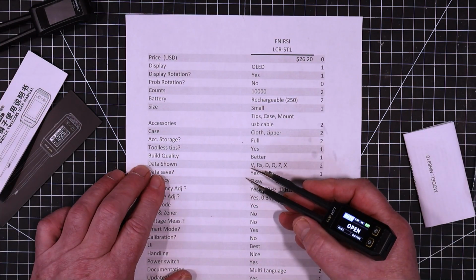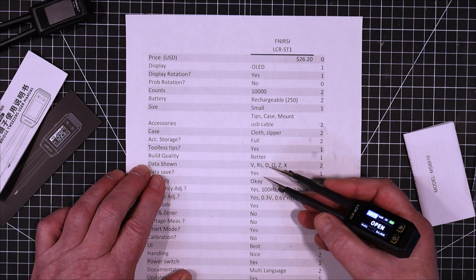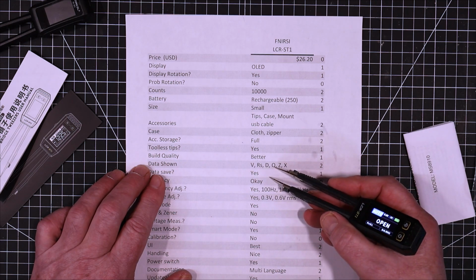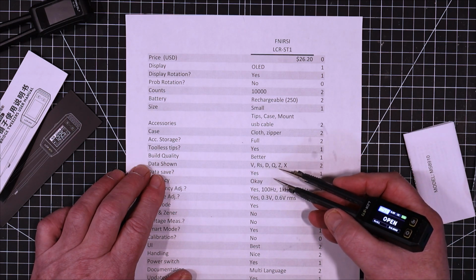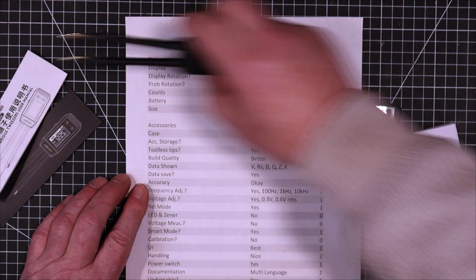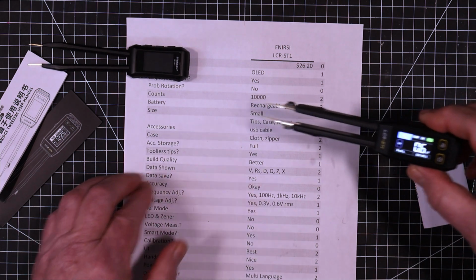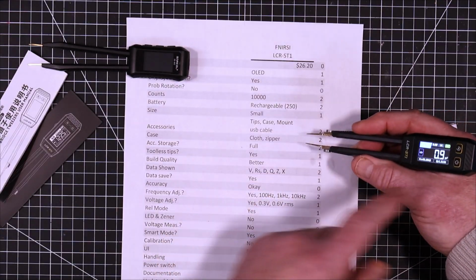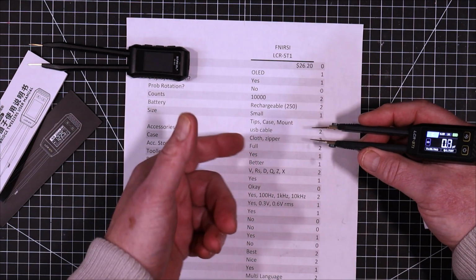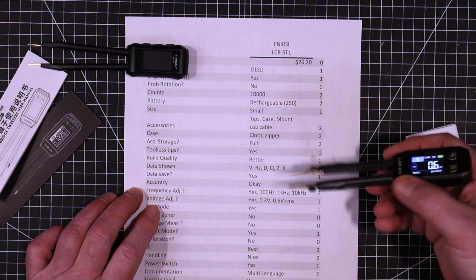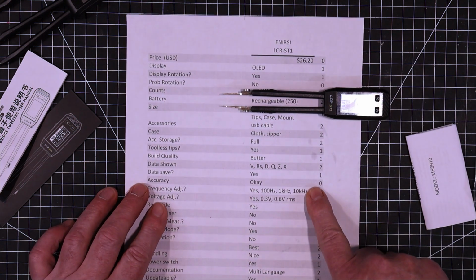Data shown, it gives you the value, it gives you the ESR, it gives you the loss angle, it gives you the quality factor, it'll give you the complex impedance, and it'll give you the reactance. It does save data just like these do, but you have to press the hold button. So you make a measurement, you press the hold button, and then it saves a record of data. And when it does save the data, it saves all of this information for each record. Accuracy, again, is okay. It meets the specifications.